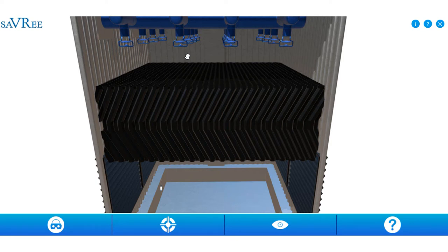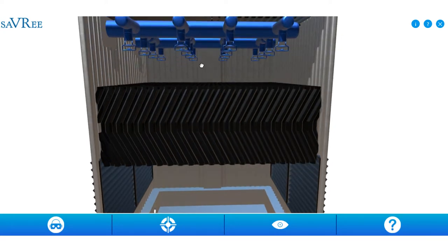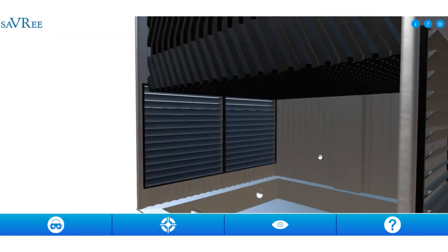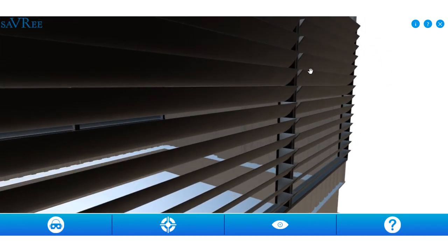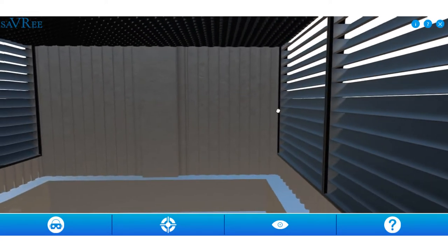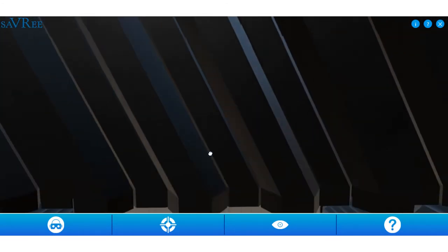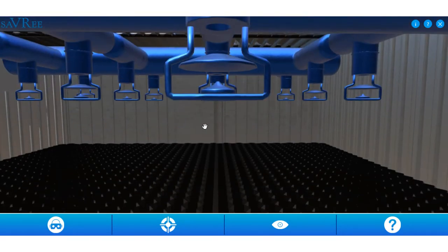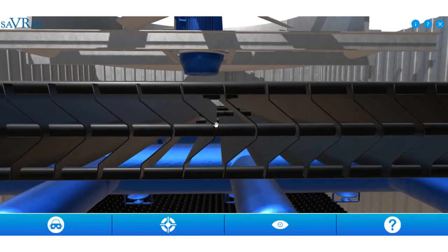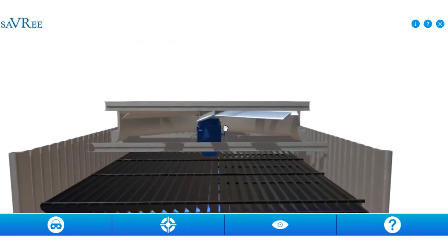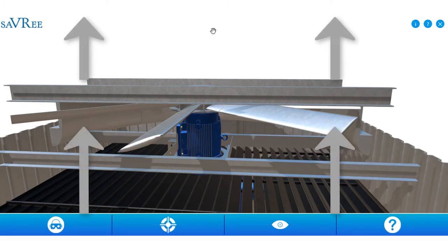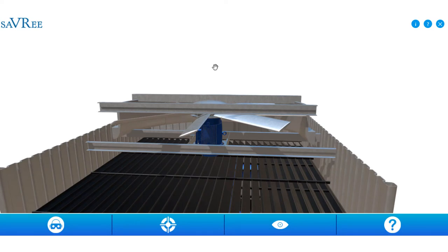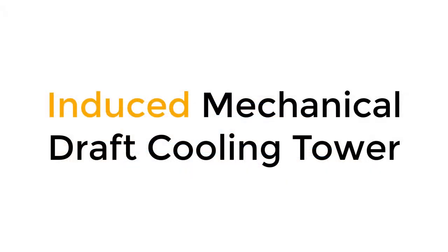There's a very good reason for this. In order to get rid of the heat that the water contains, we're going to draw air in from the bottom of the cooling tower through these little grooves, often called louvres. The air is going to rush up through the heat exchanger, all the way up, past the spray nozzles, past the drift eliminator, and out. The fan at the top is what causes this movement of air, pushing or pulling the air through the cooling tower and out the top. We call this an induced mechanical draft cooling tower.